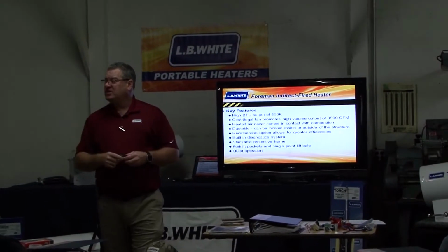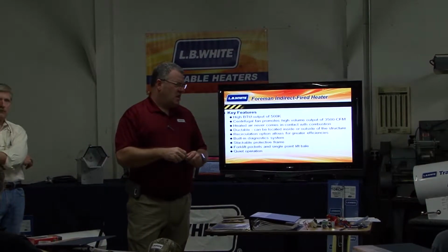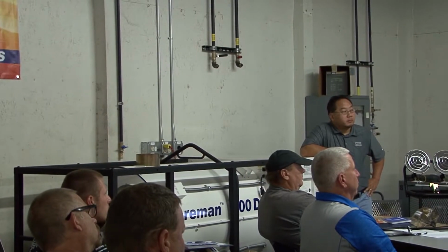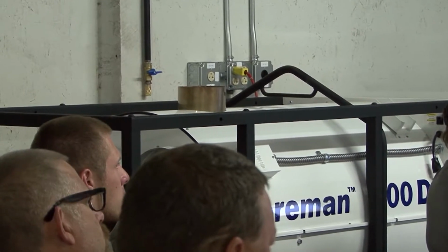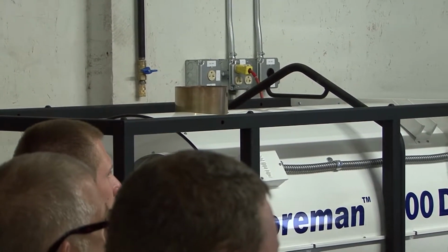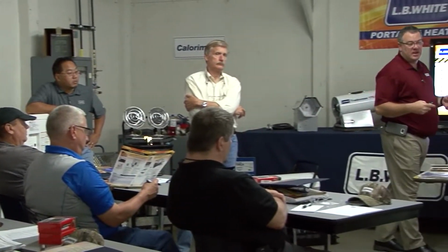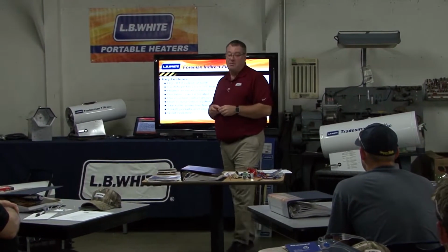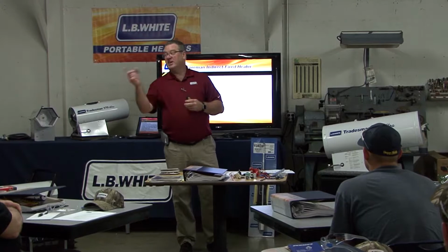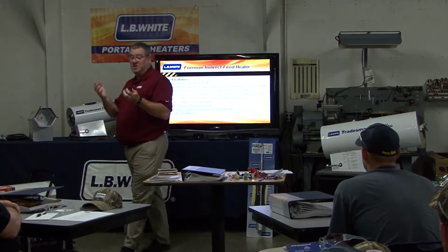Because you're venting heat out that chimney and separating that combustion process, you're venting out heat energy. So these units we say are typically about 80% efficient, roughly. You know, competitors 74. We're going to be close to 80. You know, so for every dollar you spend on fuel, you're putting 80 cents of heat into the environment, 20% is coming out of the stack. And that's just standard, normal for that kind of unit to have that kind of loss. In a direct fired system, you know, we'll tell you our premiers are 99.97% efficient. Because you're not separating that exhaust, every dollar of heat you put into it, every dollar of fuel you put into it comes out in heat.